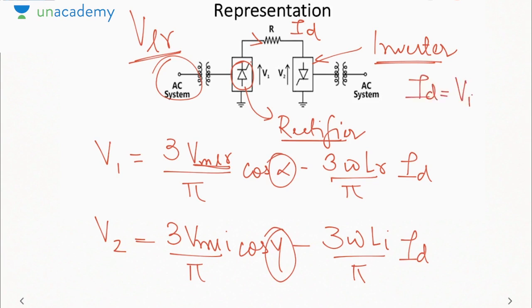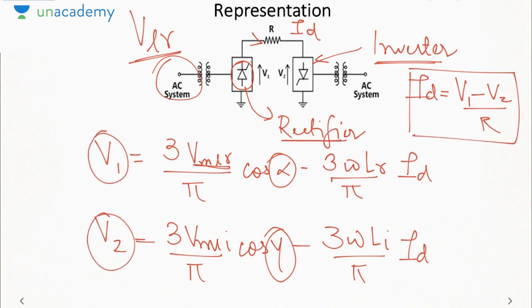ID will simply be V1 minus V2 by R. This will be the DC link current. So if you can change the voltages V1 and V2 by changing the firing angle and the extinction angle, we can also change the direction of current and the magnitude of current. Okay, so that is how we can easily control the direction of power flow and the magnitude of power flow just by controlling the firing angle, which is done by means of a control circuit in the system.